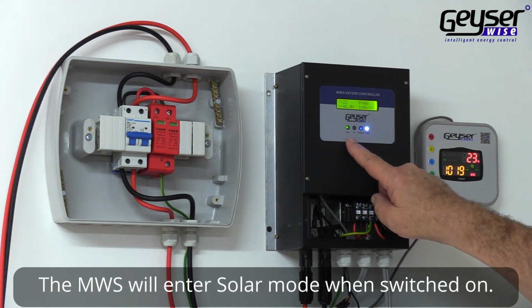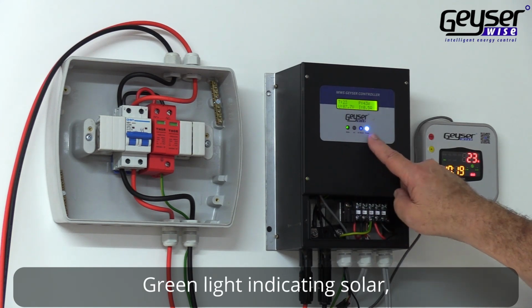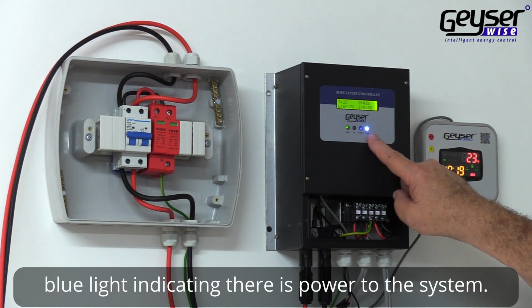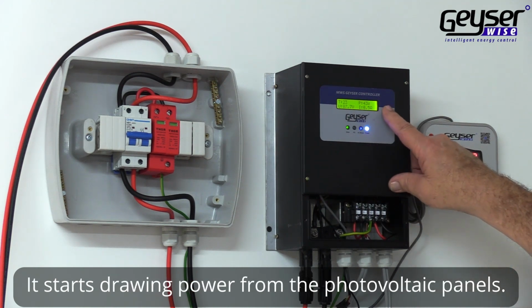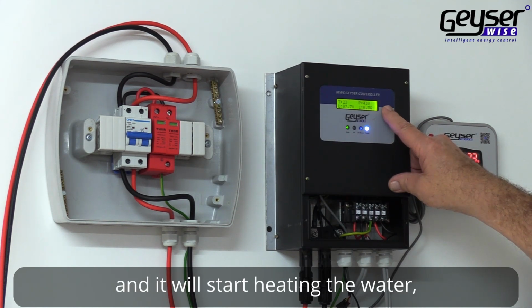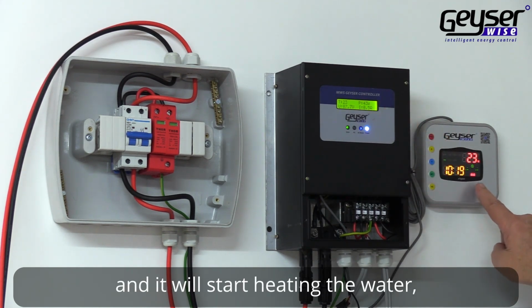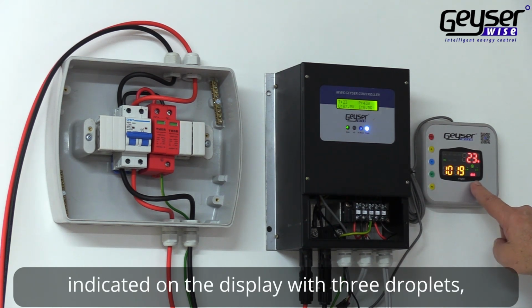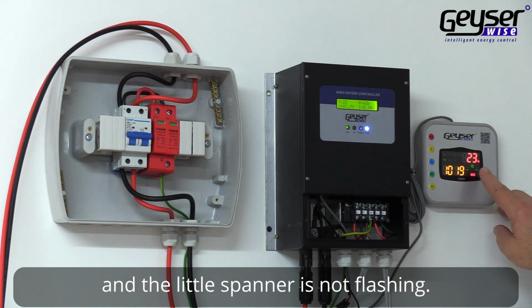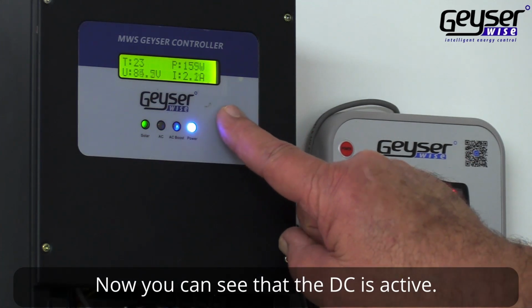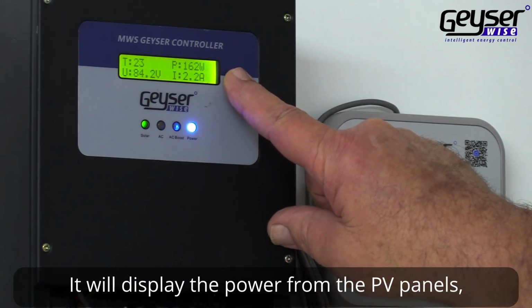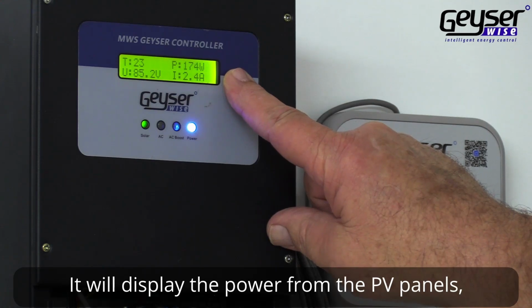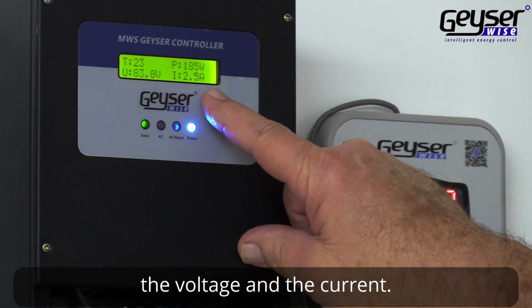The MWS will enter solar mode when switched on, with a green light indicating solar. A blue light indicates that there is power to the system. The system starts drawing power from the PV panels and will start to heat the water. This is indicated on the display with 3 red droplets and the spanner icon not flashing. Now you will be able to see that the DC is active. The power from the panels will be displayed, the voltage and the current will be shown.